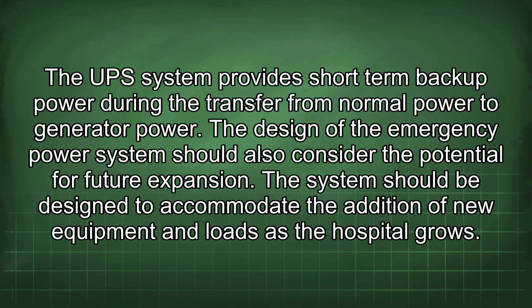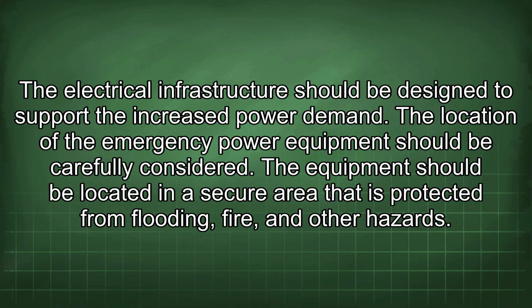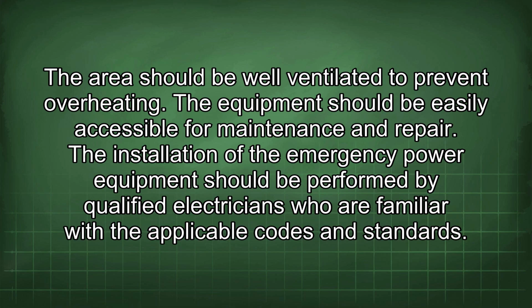The design of the emergency power system should also consider the potential for future expansion. The system should be designed to accommodate the addition of new equipment and loads as the hospital grows. The electrical infrastructure should be designed to support the increased power demand. The location of the emergency power equipment should be carefully considered. The equipment should be located in a secure area that is protected from flooding, fire, and other hazards. The area should be well ventilated to prevent overheating. The equipment should be easily accessible for maintenance and repair.